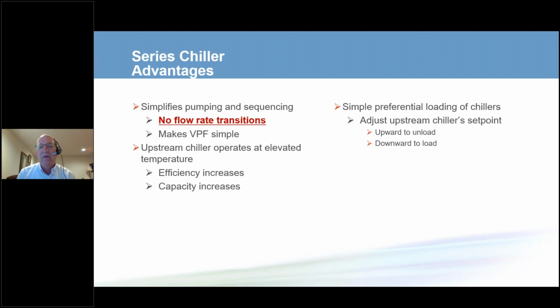But what I like best about this system is, we talked about how in a variable primary flow system, the hardest part is transitioning from 1 to 2 chillers when the chillers are in parallel, because the flow rate through the operating chiller goes down by 50%. When we put the chillers in series and turn that second chiller on, there is 0 flow rate transition. We got rid of the hardest part of a variable primary flow system by mixing the lower flow rates, higher delta T, and variable primary flow, and then putting them in series.